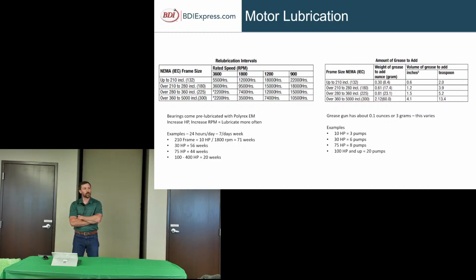But for example, most of your guys' fans are running 24/7. If you guys are in hospitals, I would imagine 24/7. Schools, maybe not so much. I'm kind of the guy that when I get a box of Legos, I'm trying to build it without my instructions. All these motors do come with manufacturer instructions for lubrication, but it's not going to be lubricated as much as you would a mounted pillow block bearing or a mounted bearing. So always pay attention to what the manufacturer recommends, and always pay attention to what grease you are putting in there. Greases don't mix. I'll go into that a little bit.